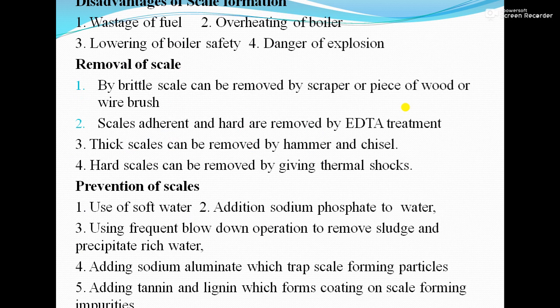Next is removal of scale. First, brittle scale can be removed by a scraper, piece of wood, or wire brush. Second, it can be removed by treatment with EDTA, which dissolves the calcium and magnesium salts present in the scale. Third, thick scale can be removed by hammer and chisel. Fourth, hard scale can be removed by giving thermal shocks.